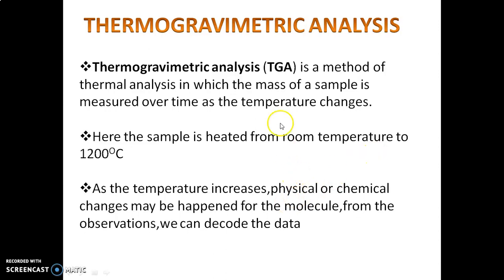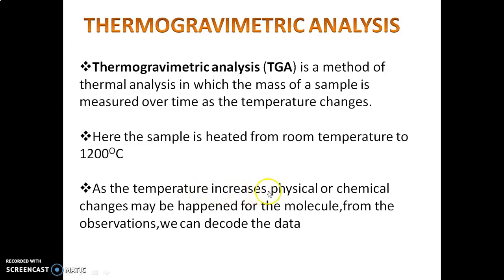According to the definition, thermogravimetric analysis is a method in thermal analysis in which the mass of the sample is measured over time as the temperature changes. Normally, the sample is heated from room temperature to 1200 degrees Celsius. As the temperature increases, physical or chemical changes may occur.